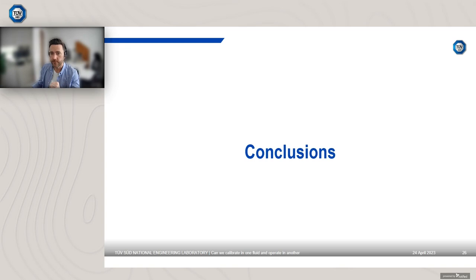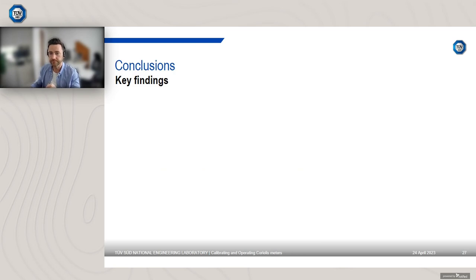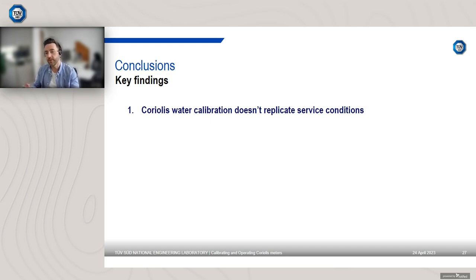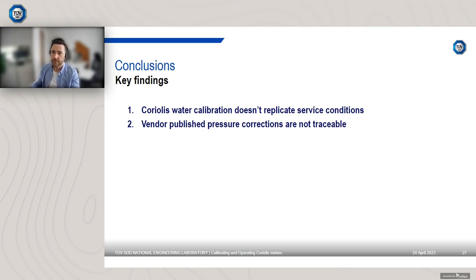Now, coming up to the overall conclusions, then I'm going to touch on some of the questions, because there's several have come in, which is good. So some of the key findings. We often get asked this: can a water calibration replicate service conditions? So can I simply calibrate my Coriolis meter in water and then operate at elevated viscosity or elevated temperature and pressure? My answer to that is no, it doesn't fully replicate it, but it depends on your measurement uncertainty.